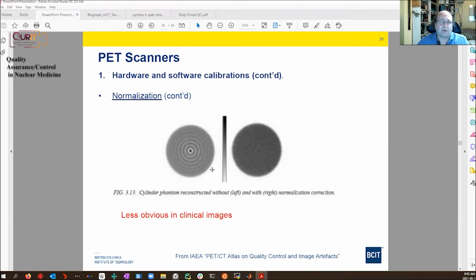Here's an example of why it's important. This is a reconstructed image of one slice of a uniform cylinder. This is what it should look like. You see uniform count density. If you've got some significant variations in the efficiency of detector pairs, those variations somehow, by the magic of reconstruction, get transformed into circles in the reconstructed slice. If you see a lot of them, we sometimes call it a bullseye artifact. It's less obvious in clinical images, more obvious here. And this is why another type of quality control would be actually measuring the uniformity of a reconstructed slice. Even though NEMA doesn't have that as part of their protocol, it should be done.